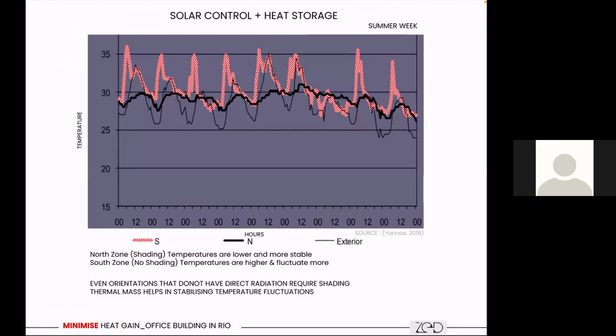This is a pure example of the heating and cooling load of a non-shaded and a shaded building with or without thermal mass. A glass building follows the profile of the external temperature because of having very little mass, whereas a building with thermal mass tries to maintain a straight line, avoiding overheating during peak hours and providing comfort. It stays below 30 degrees predominantly throughout the day, and this is purely because of your material choices, orientation, and shading design.